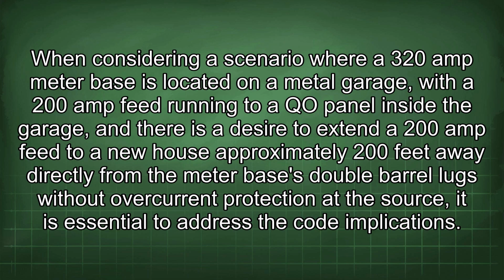When considering a scenario where a 320 amp meter base is located on a metal garage, with a 200 amp feed running to a QO panel inside the garage, and there is a desire to extend a 200 amp feed to a new house approximately 200 feet away directly from the meter base's double barrel lugs without overcurrent protection at the source, it is essential to address the code implications.